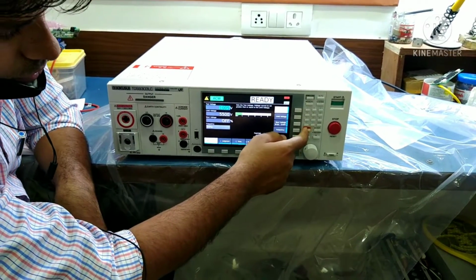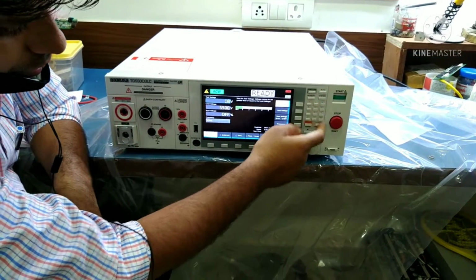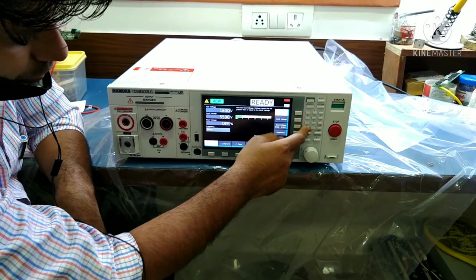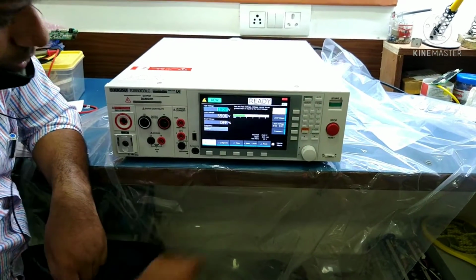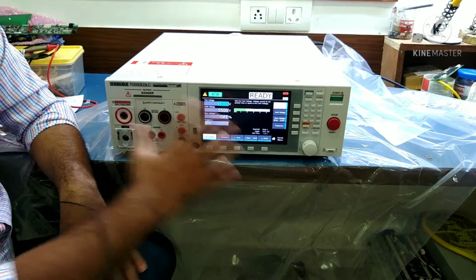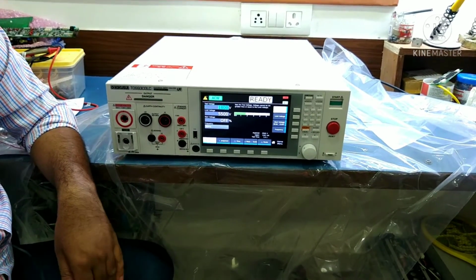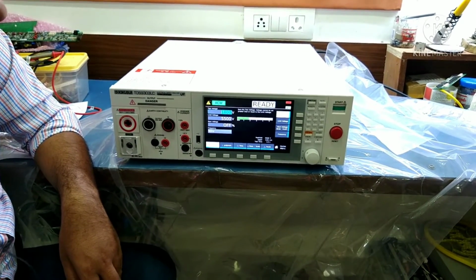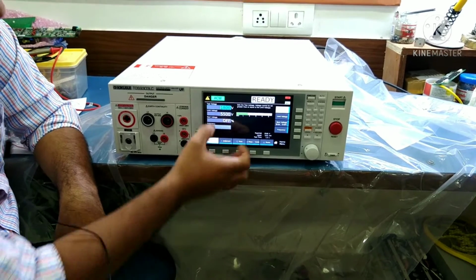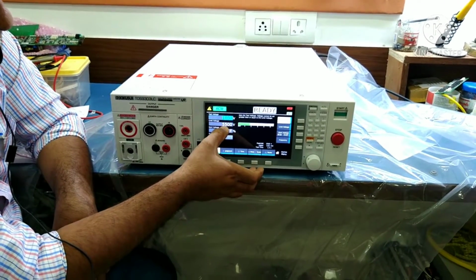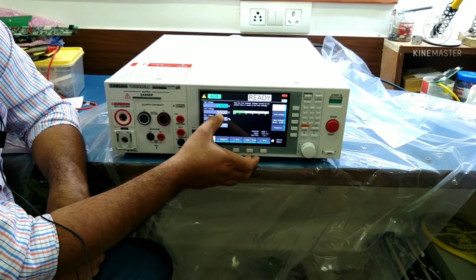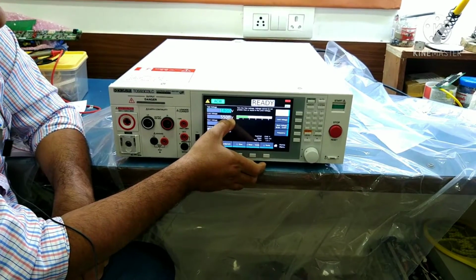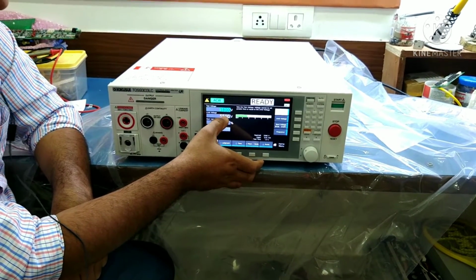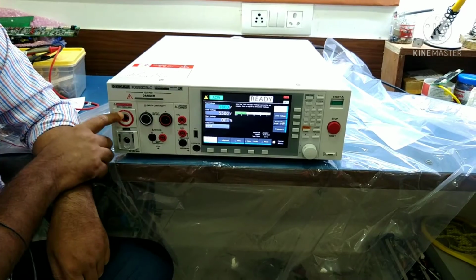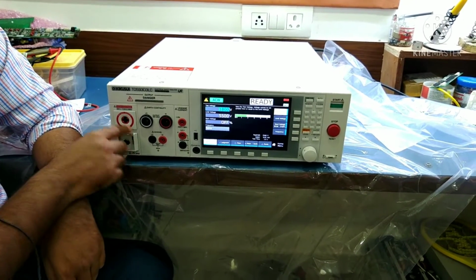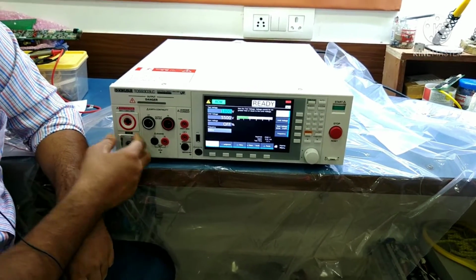1800. Then press enter. Now it is set, so there is no need to press any extra keys to save the data. This is the maximum limit, that is 5500 volts AC. This is 110% of its capacity. The maximum capacity we can take the voltage from the ACW is 5 kV.